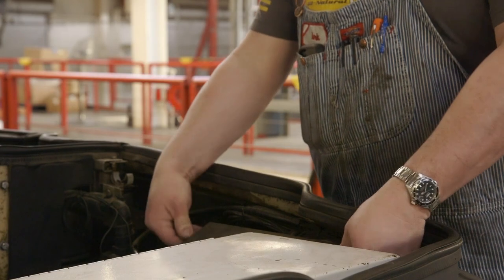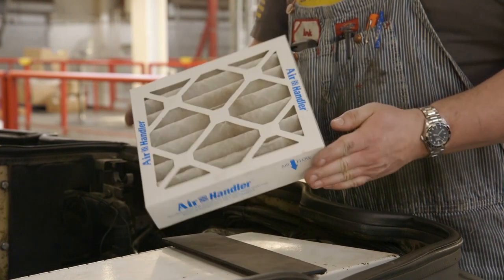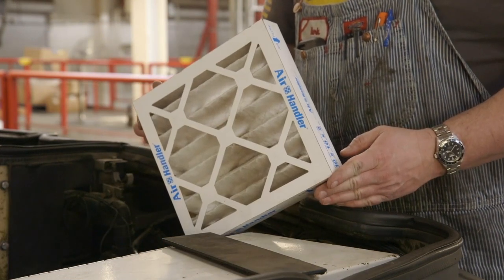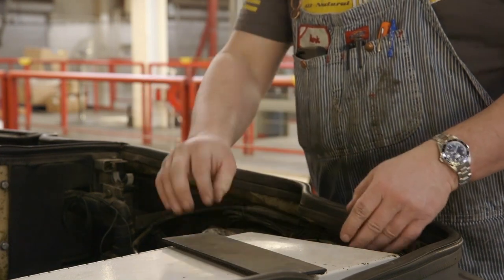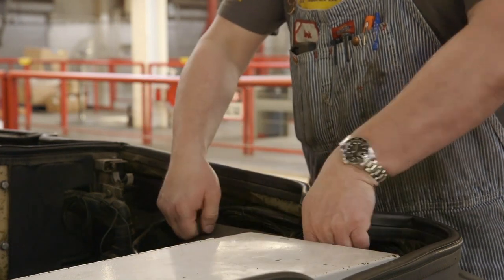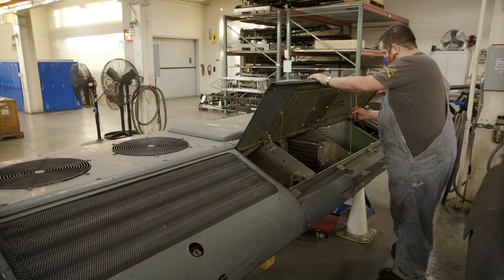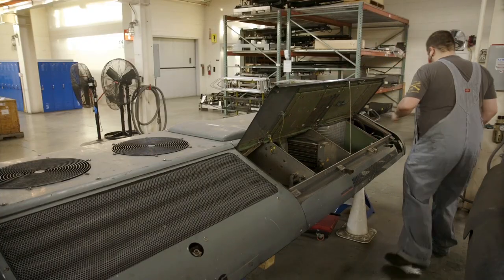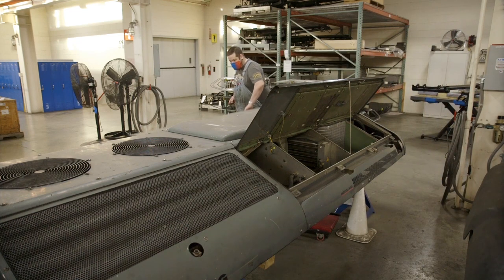Under normal conditions we change them out every 90 days. But 2020 has been real interesting with the wildfires and the current health situation. We changed them right after the fires ceased, which proved to be critical — we caught a lot of ash and debris in the filters in a short period of time, and it prompted us to do two fleet-wide filter change outs.